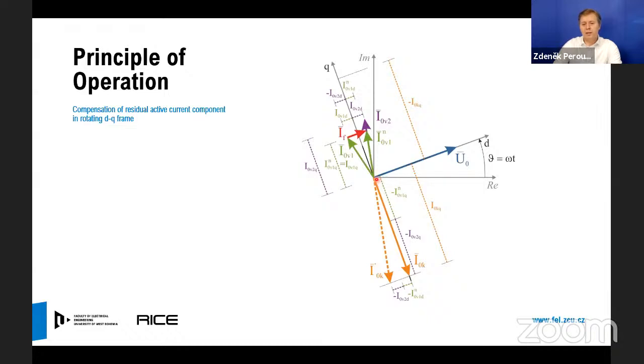What we can see on the next slide is that if we operate only the arc suppression coil, the arc suppression coil is, depending on the zero sequence voltage, able to generate the inductive current, which acts against the fault current, which is in this quadrant. In our case, we are able to shift and adjust the compensation current, and we are able to fully compensate the fault current, including its active component, as well as higher harmonics, which is very important.